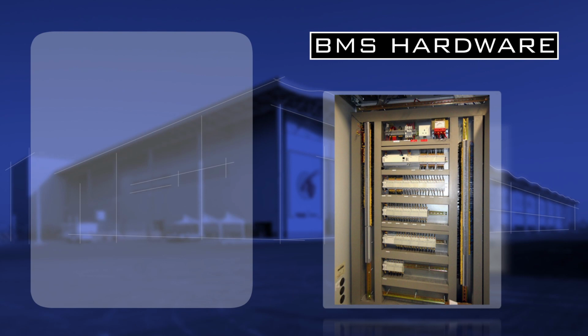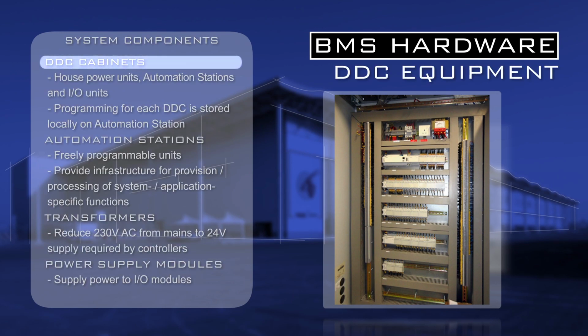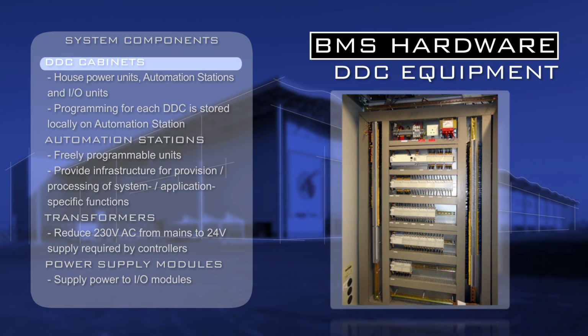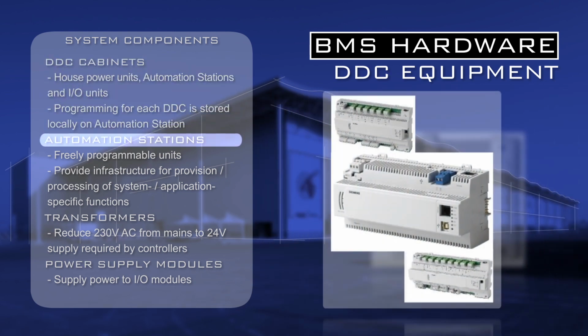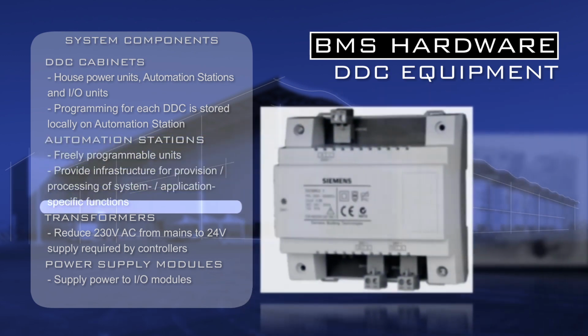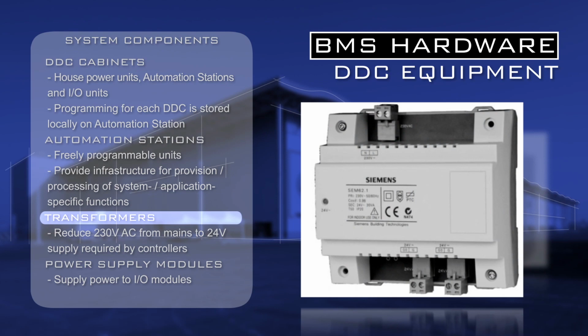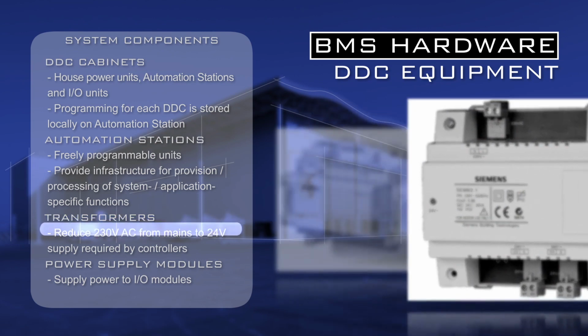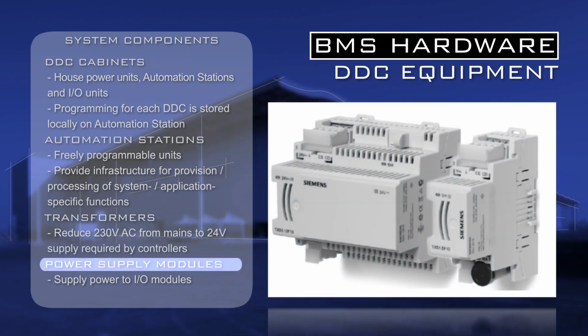BMS hardware consists of a number of components: DDC cabinets, which house the power units, automation stations, and input and output units. Programming for each DDC is stored locally on the automation station. Automation stations, which are freely programmable and provide the infrastructure for the provision and processing of system and application-specific functions. Transformers, which reduce 230 volt AC from mains to a 24 volt supply, which is required by the controllers. Power supply modules, which supply power to the input and output modules.